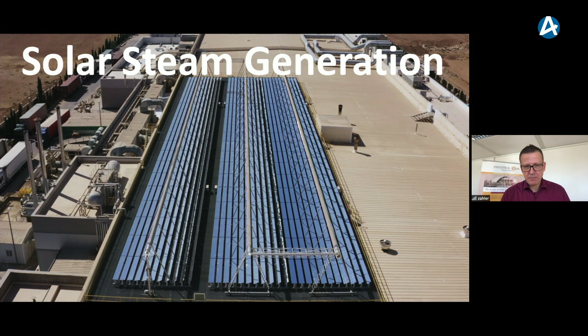This is how we all started—how Industrial Solar GmbH began its activities, with a concentrating solar thermal technology called a Fresnel Collector. Here you see an installation in Amman, Jordan. This system, with more than 1,200 square meters, generates temperatures up to 225 degrees Celsius and pressures up to 25 bar max. It feeds steam to a tobacco plant, and part of the steam is used for an absorption chiller with about 540 kilowatt cooling capacity.